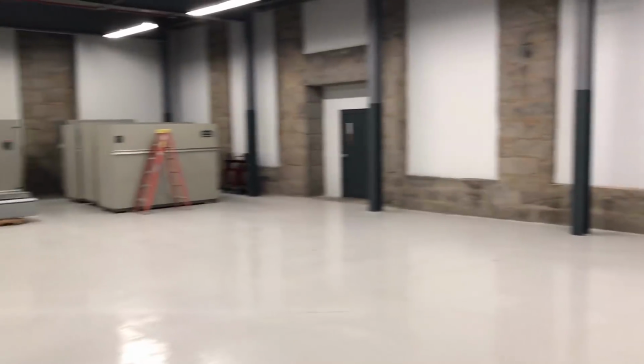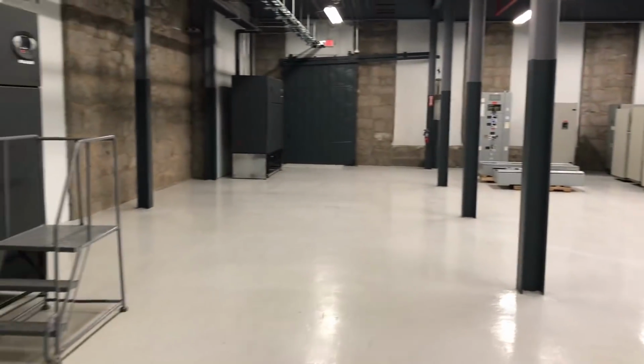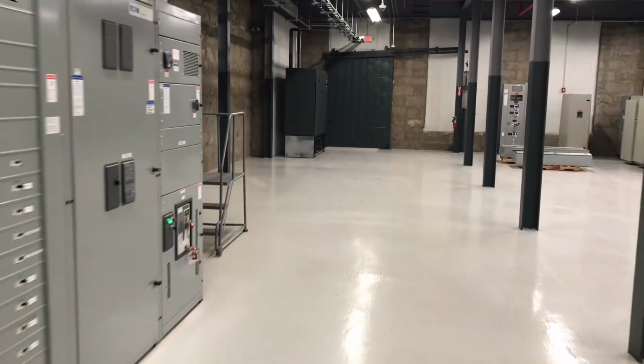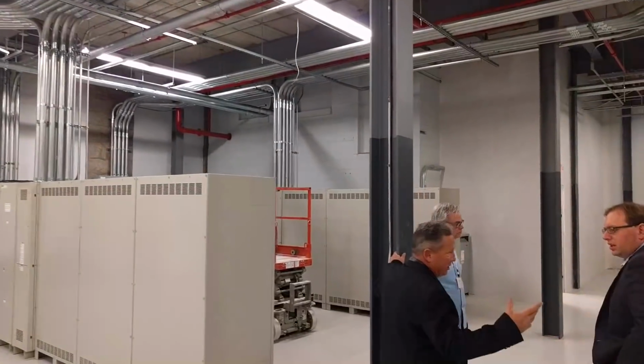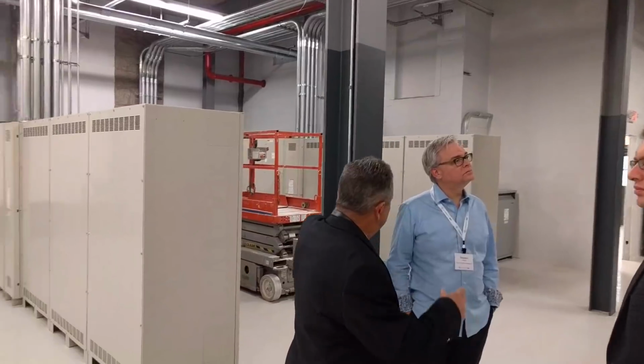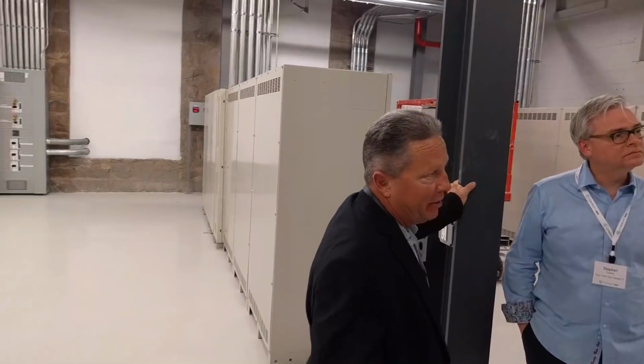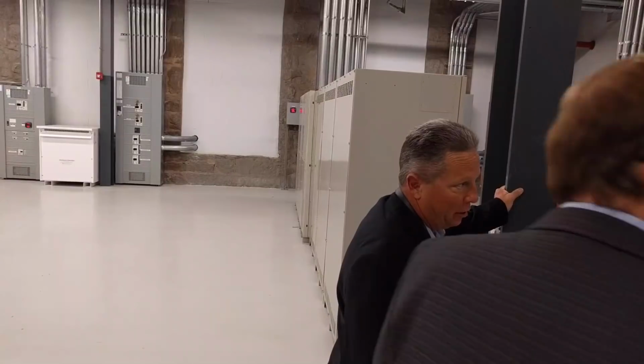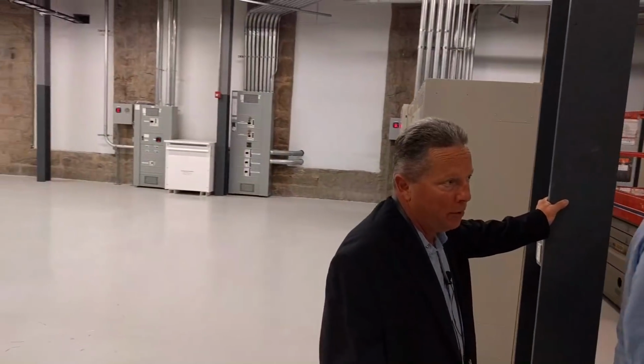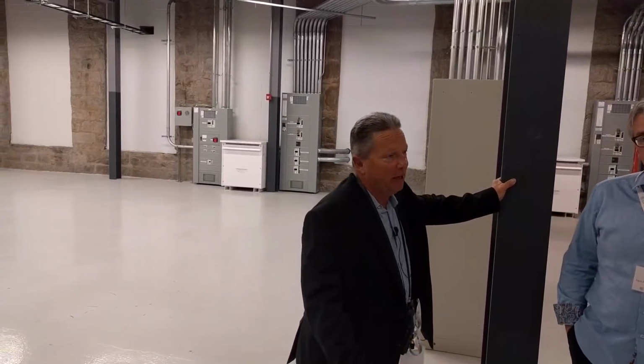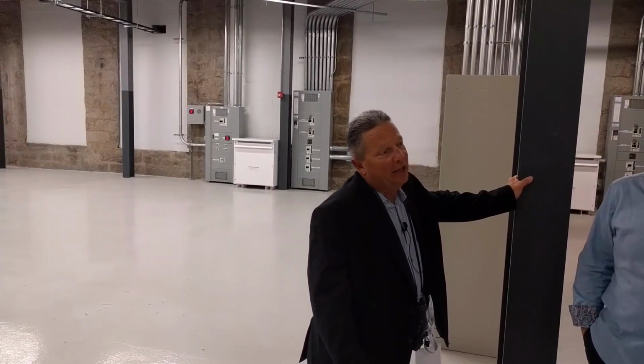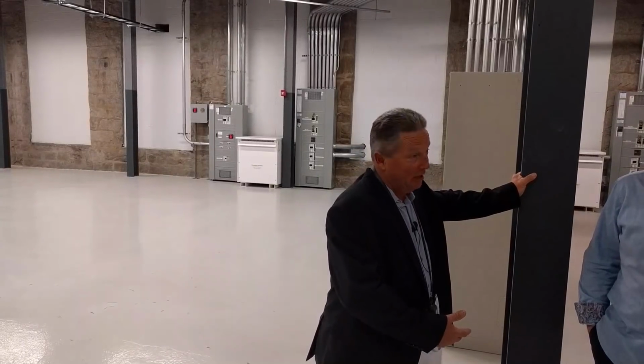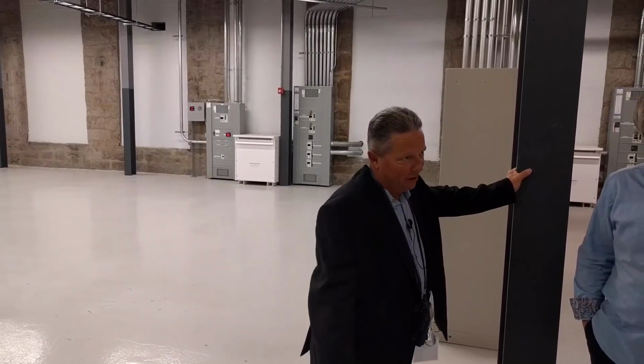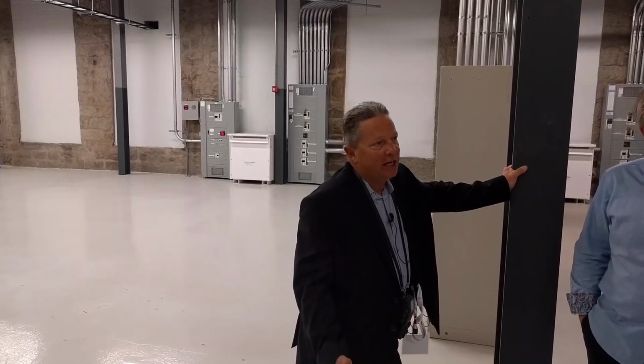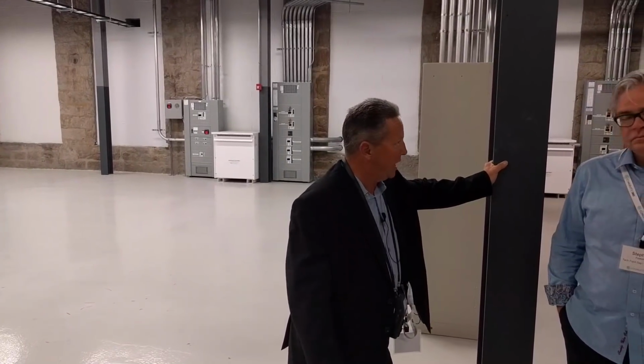So this is a main switchboard, motorized breakers. Connected to this switchboard are 2 UPSs and 2 generators and the utility feeds. Each UPS has 3 battery cabinets. A battery cabinet gives you 3 minutes of run time without generator or utility. So each UPS has 9 minutes of battery time. If A is backing up B, it gives me 18 minutes of battery time, and that's if they're 100% loaded. They're not 100% loaded, so I have oodles of backup time. In reality, it takes about 5 seconds for the generators to ramp up to speed and take over the entire load.